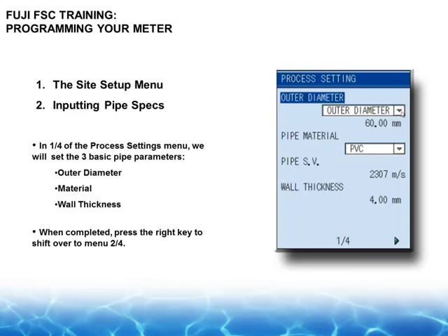And this is the area where most people make the biggest mistake. They make the biggest mistake because they put bad data in. Every meter goes out the door with an ANSI pipe chart book. You can also download it from our website, and it's included in the big manual as well. If you have a certain pipe size, you have to put the correct pipe size in. This is not a piece of lumber. This is not a 2x4, and by the way, a 2x4 is no longer a 2x4. Someone would have a 3-inch pipe, for example, and they'd put 3-inch in for a carbon steel pipe. The ANSI pipe chart book for a carbon steel 3-inch pipe says 3.5 OD. Wrong data in, bad data out. Put the right pipe size in, you get good data.